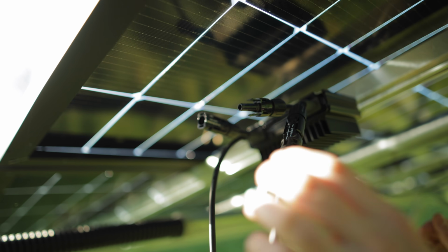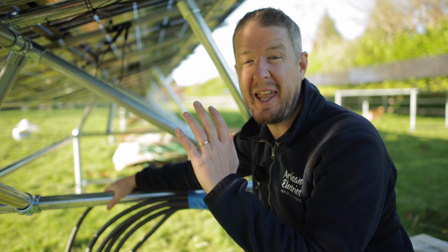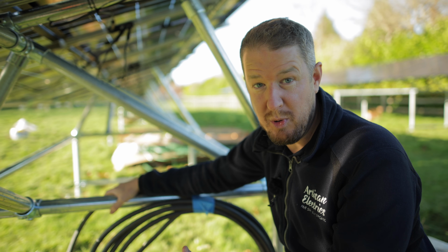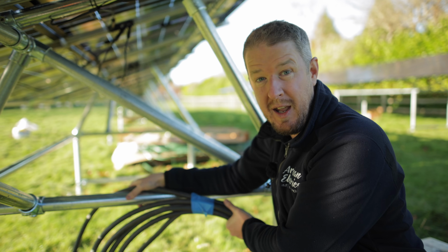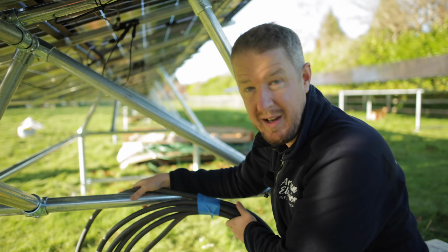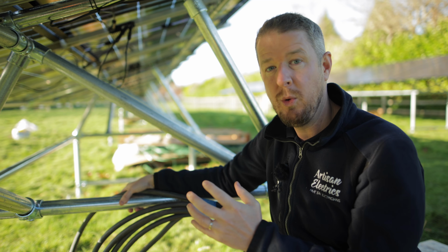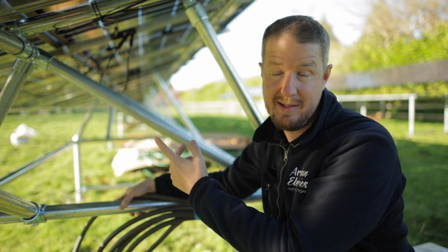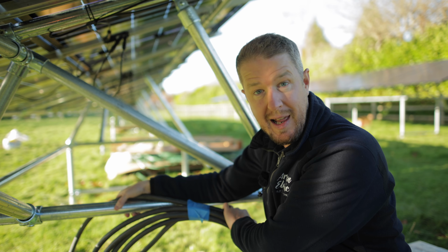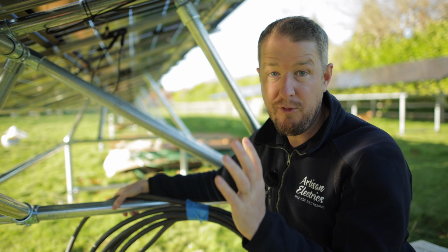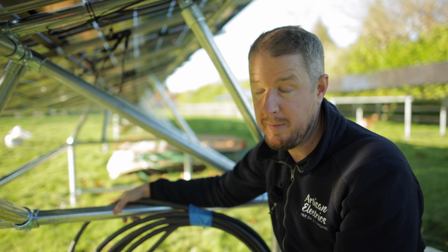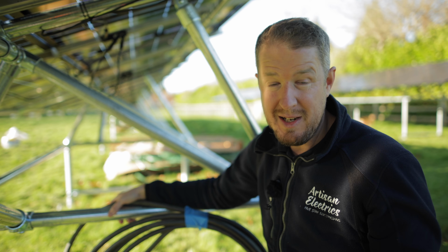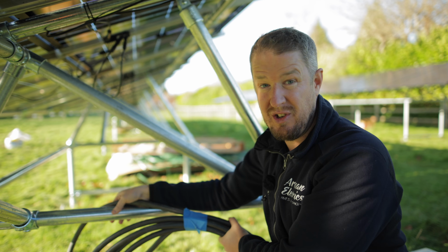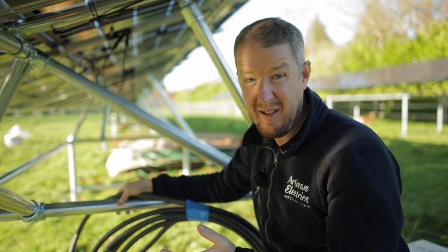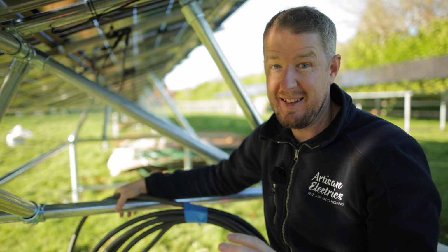The Impact Moling team have installed over 1 kilometre of cables on this project. This cable here, which we call PV Ultra, is a DC armoured cable. It goes all the way back to the inverter and the stables, and each length of it is 200 metres. We've got 4 lengths of 2-core 6mm PV Ultra - 800 metres of this cable alone - and it's literally nearly £10,000 worth of cable just for this. It's a ton of money.